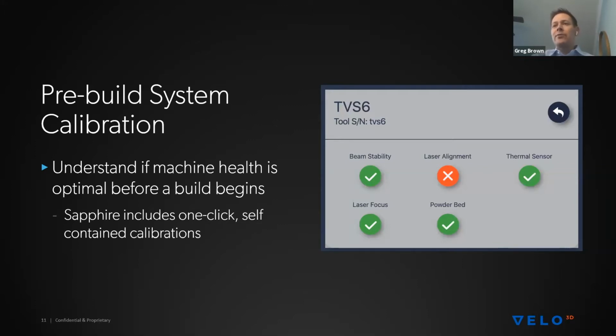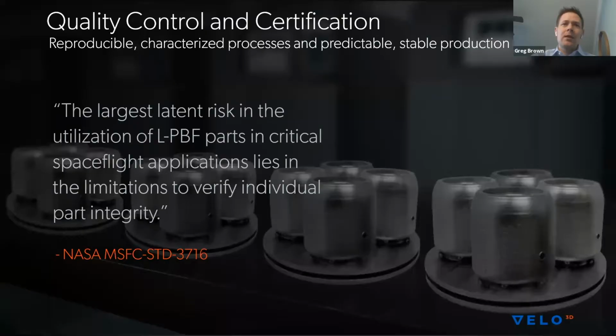And so on the print software itself, there's a page for calibrations, and basically there's a series of buttons for all of these different tests that you can run. If you walk up to the tool, the operator can just press those individual buttons and it automatically runs through a routine that does a self-calibration of the system. And then the results of which are reported back to Assure. So Assure can say, yes, the system is in spec for these different subroutines, or flag if something is out of spec. And I'll walk through what all of them are in the next slides.